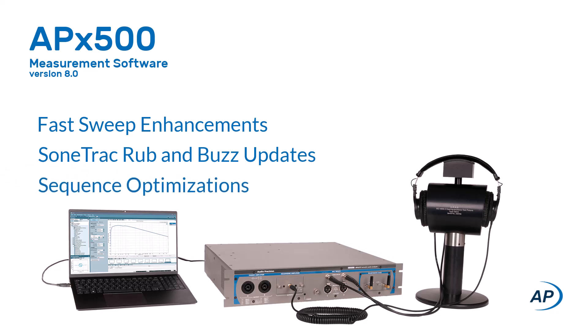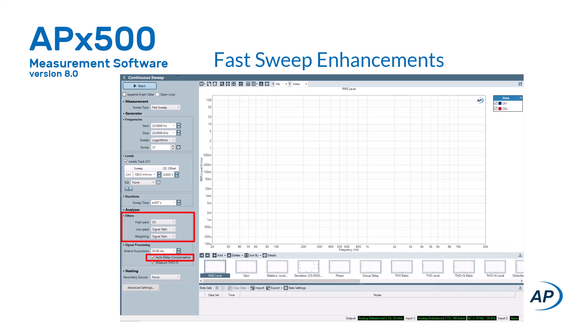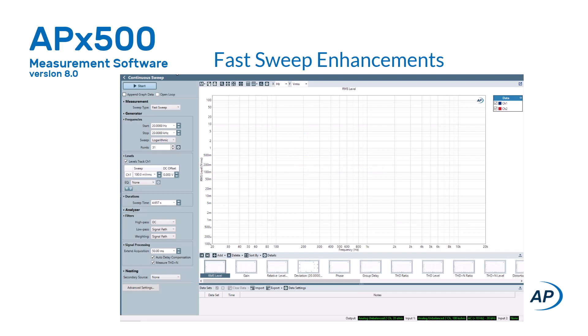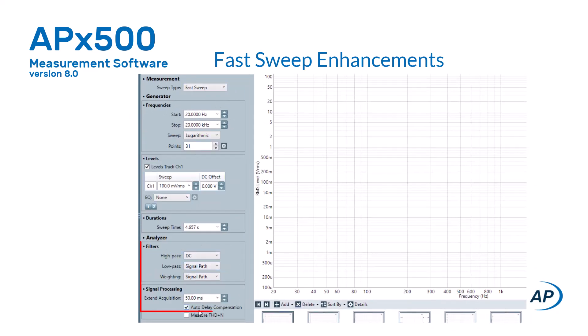Let's take a quick look at each of these feature enhancements. For THD+N level and ratio results, measurement-specific filtering options and automatic delay compensation capabilities have been added to acoustic response, continuous sweep, and loudspeaker production test measurements when using a fast sweep stimulus. Using the fast sweep stimulus for THD+N level and ratio measurements provides a significantly faster measurement time compared to standard step sweeps. When fast sweep is selected, the filtering and auto delay compensation options are available in the measurement panel, allowing you to set local high-pass, low-pass, and weighting filters for the selected measurement.